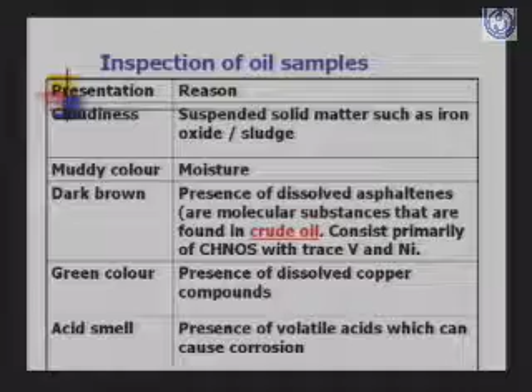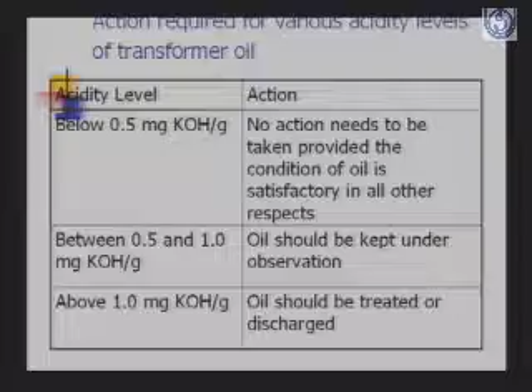Then we test the acidity level of the oil. If the acidity level of the oil is found below 0.5 mg KOH per gram, then no action needs to be taken, provided the condition of oil is satisfactory in all other respects which we had seen earlier. But if the acidity level is found between 0.5 and 1.0 mg KOH per gram, then the oil should be kept under observation. And if it is above 1.0 mg KOH per gram, then the oil should be treated or discharged. It has to be treated again.